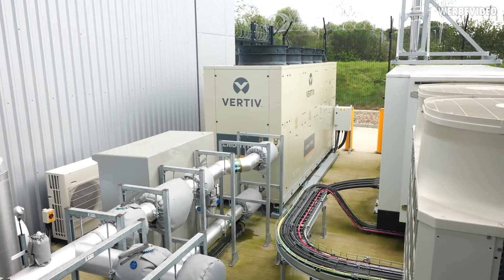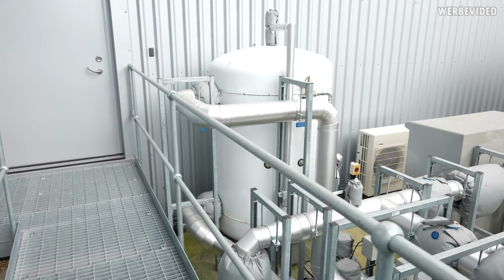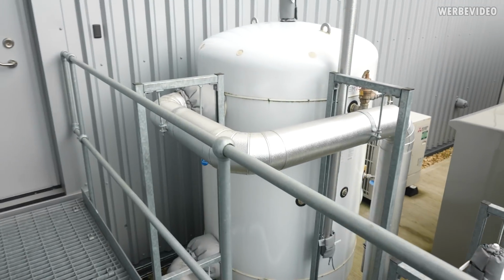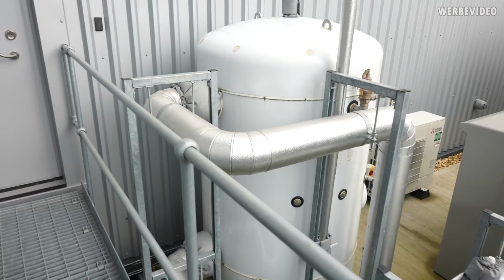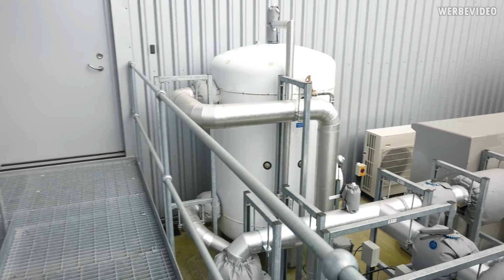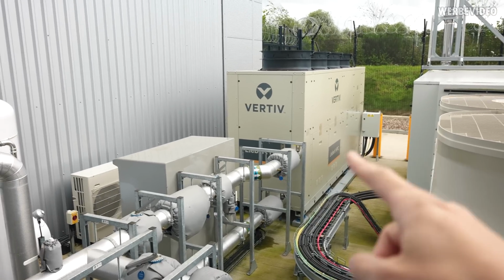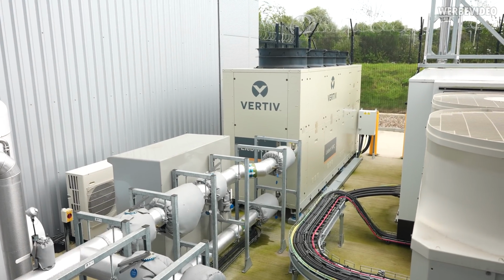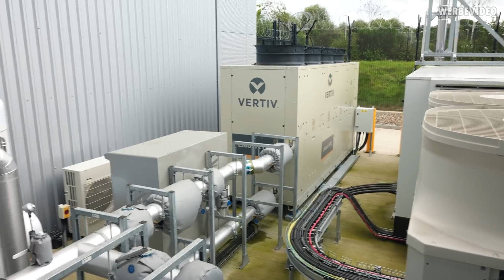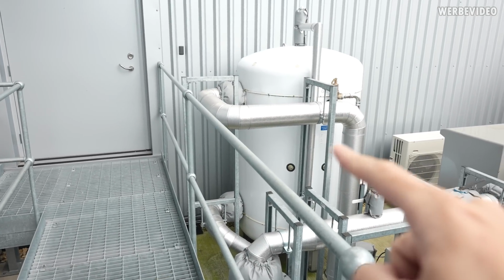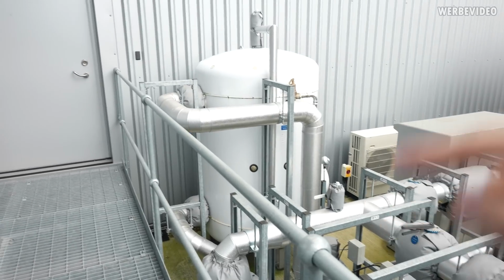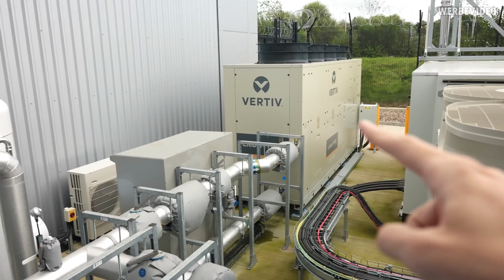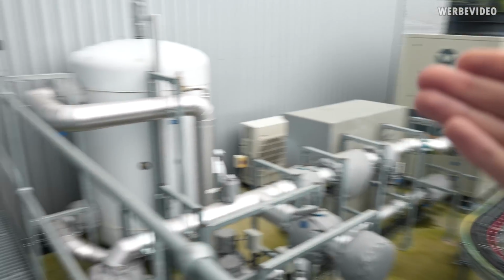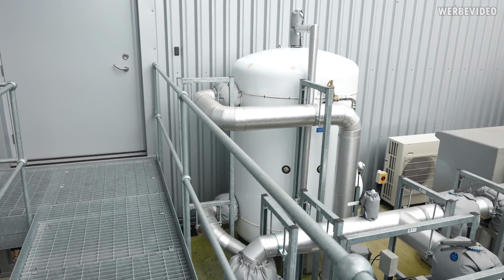One interesting aspect here relates to the Tier 4 certification, which is where this big reservoir comes into play. I thought it would just be a normal reservoir for the entire water loop, which might be necessary, but this setup is already quadruple redundant, so if it fails there are still other chillers that could jump in. But if everything else fails, there's this big tank containing cold water, normally just part of the cold water loop, that can be used to cool the chiller as a last resort. That's an additional requirement for the Tier 4 certification.